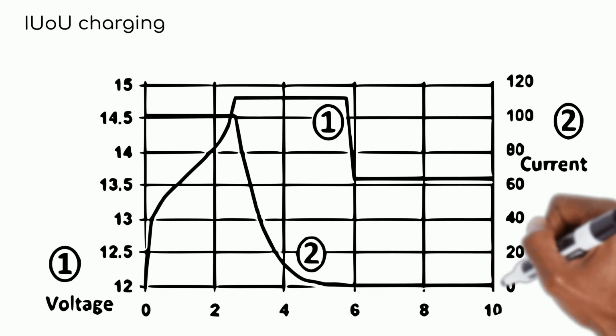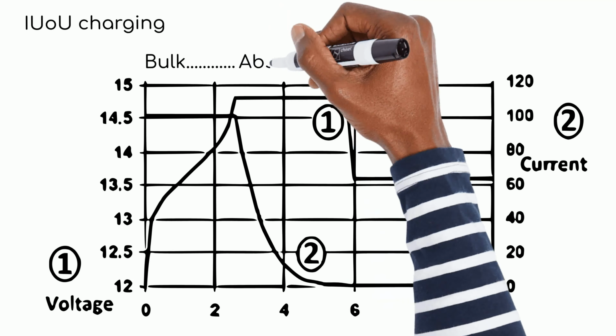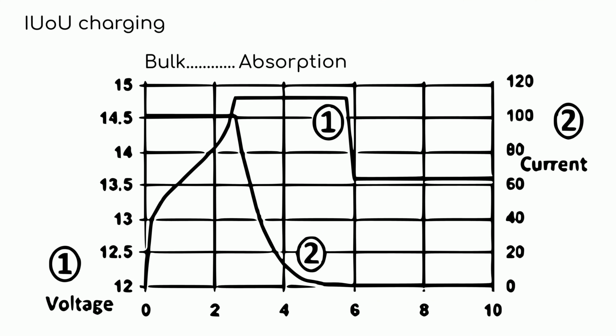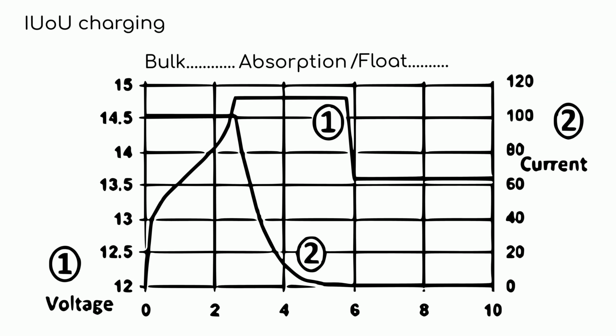First, the batteries are charged to the required voltage with the maximum possible current. Then they switch to the absorption mode, when the charging current gradually drops and the voltage remains at the same level. Just at this moment, it is ideal to start balancing the cells in parallel. And then the transition to float mode follows.